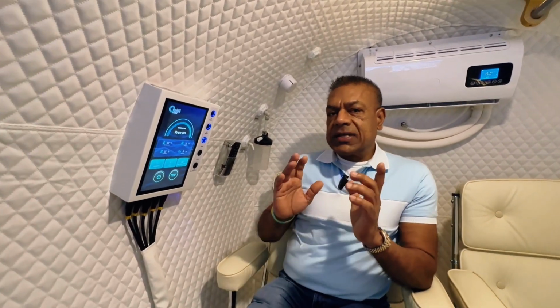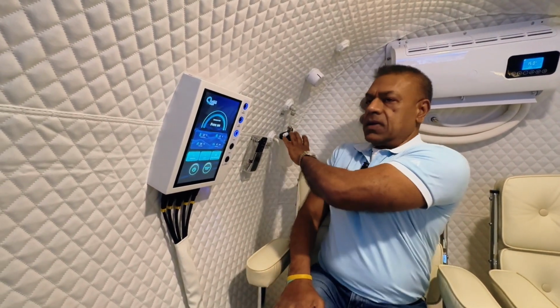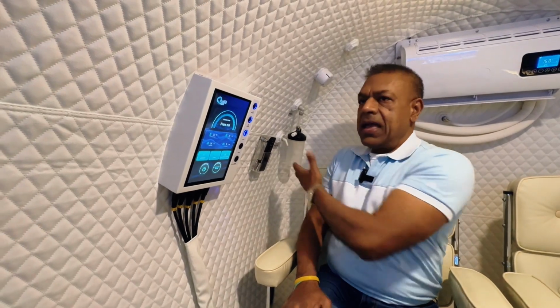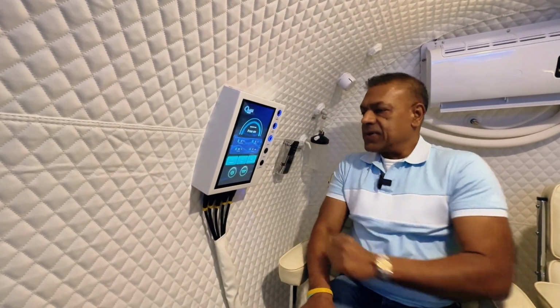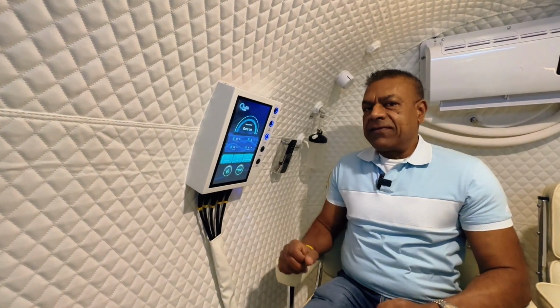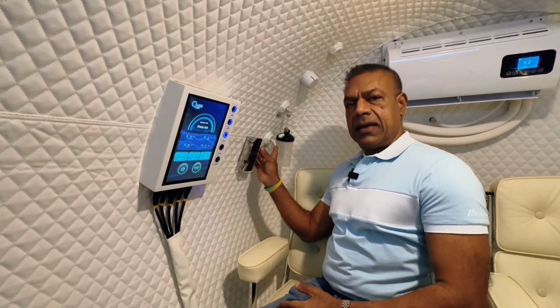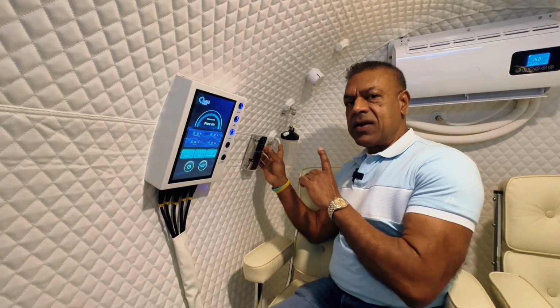Now let's go over some of the internal features. You have two sets of compressors here, one compressor that would be pressurizing through here with the condensation cup, and then the one exactly on the opposite side from this direction. You also have two sets of oxygen sources. The first oxygen source is right here, and then a mirror image of that would be on the other side, such as right there.